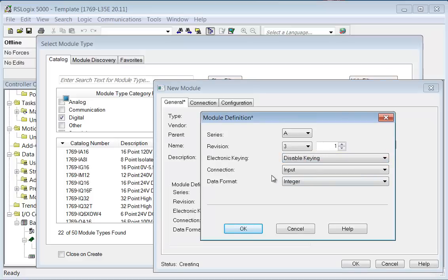In the old days, keying literally was a key. In each I/O module, each separate part number had a notch, a little slot cut into its circuit card edge that slid into the connector on the back plane in the chassis, and that notch was at a different location for each individual module. So when you bought the module, it came with these little plastic keys, and you reached back there into that slot and you placed it in the right position so only that part number module could slide in there. That was called keying. Well, we don't do that anymore.